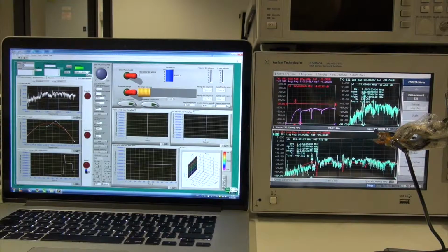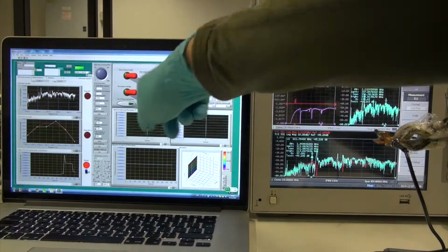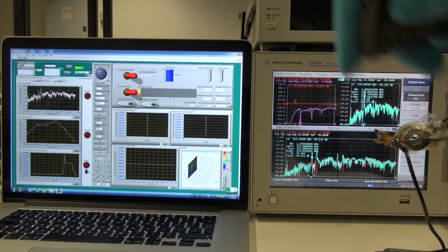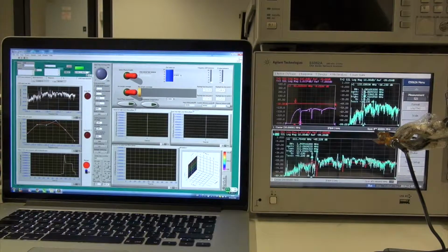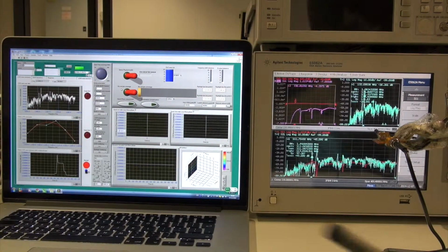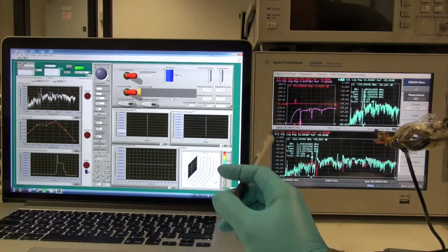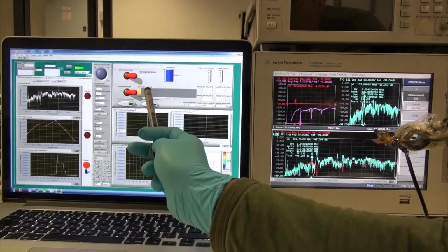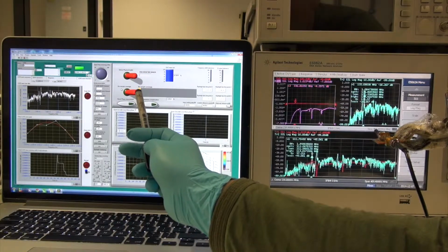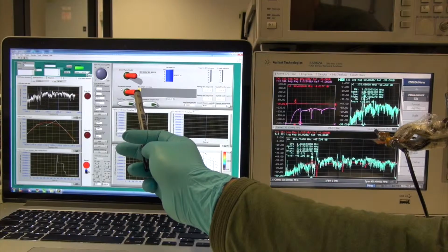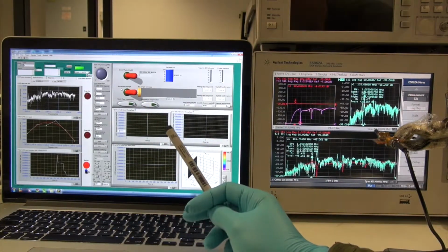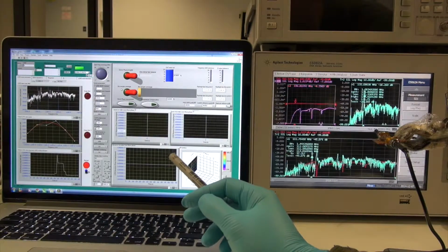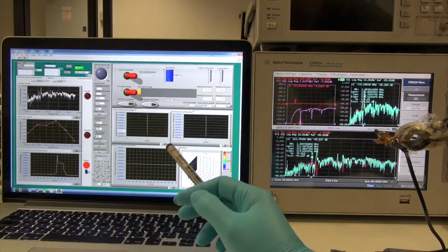Then we can see a further recovery of the surface. So for this specific device, after the Love wave fully recovered, the Rayleigh wave amplitude still didn't fully recover to 100%. That means this device has some dust on the surface because it's not always in a clean environment. It needs a deep cleaning.